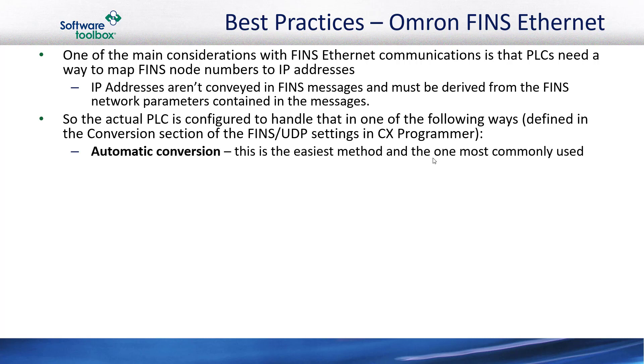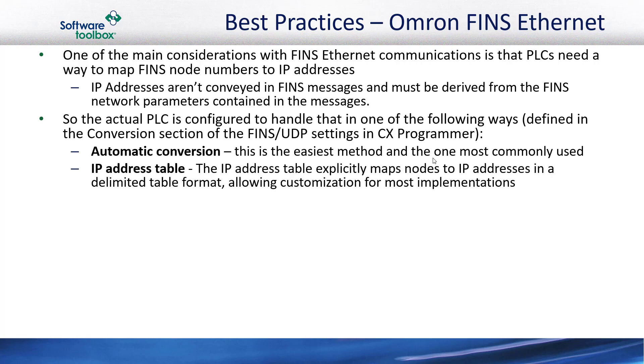The first method is the automatic conversion method, and this is the easiest method and the one most commonly used. The IP address table method is where the IP address table in the controller explicitly maps nodes to IP addresses in a delimited table format, allowing customization for most implementations. The third option is the combination method, which uses both automatic conversion and the IP address table.